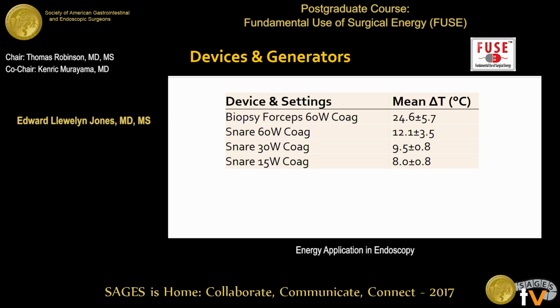We looked at different devices and activated them within the channel just to see what the highest risk device to use is, and it's the biopsy forceps. We activated it on 60 watts coag so we could see what was going on, and it increased our tissue temperatures by 25 degrees. That's, again, well over the threshold of 60 degrees. You can be causing significant injury.